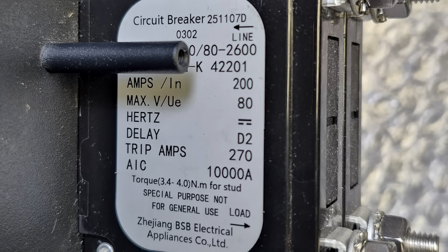But then we've got a rated current of 200 amps, a maximum voltage of 80 volts. Hertz, so the frequency is DC, so it's DC rated. The delay is D2, whatever that means. The trip current is 270 amps here. That is interesting.